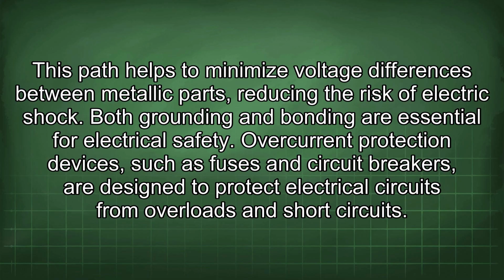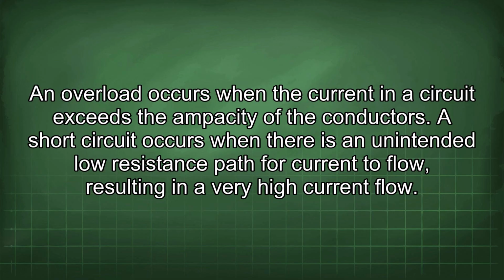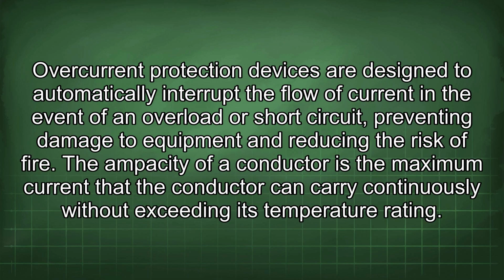Overcurrent protection devices, such as fuses and circuit breakers, are designed to protect electrical circuits from overload and short circuits. An overload occurs when current in a circuit exceeds the ampacity of the conductors. A short circuit occurs when there is an unintended low resistance path for current to flow, resulting in a very high current flow. Overcurrent protection devices are designed to automatically interrupt the flow of current in the event of an overload or short circuit, preventing damage to equipment and reducing the risk of fire.